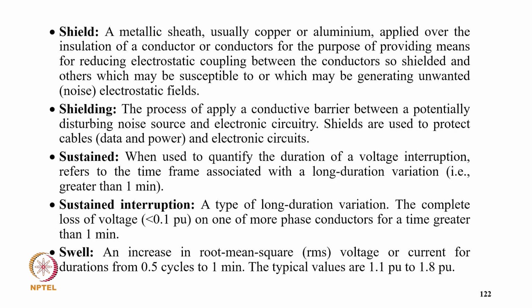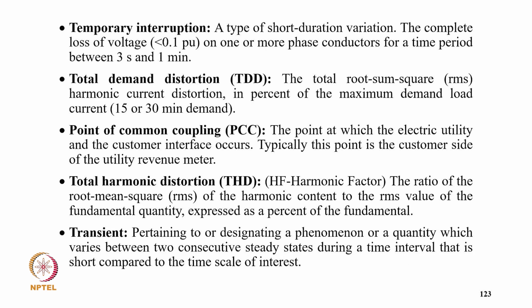Sustained: when used to quantify the duration of a voltage interruption, it refers to the time frame associated with long duration variation, greater than 1 minute. Sustained interruption: a type of long duration variation, the complete loss of voltage, less than 0.1 per unit, on one or more phase conductors for a time greater than 1 minute. Swell: an increase in the root mean square voltage or current for a duration of 0.5 cycles to 1 minute. The typical value is 1.1 to 1.8 per unit. Temporary interruption: a type of short duration variation, the complete loss of voltage, less than 0.1 per unit, on one or more phase conductors for a time period of 3 seconds to 1 minute.